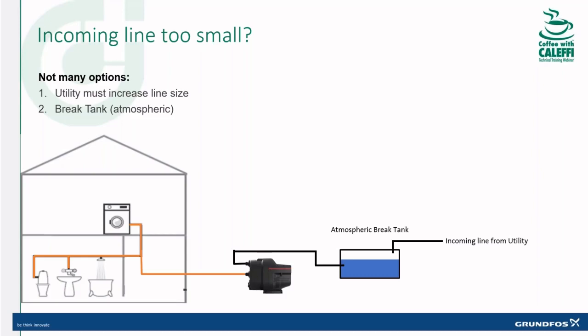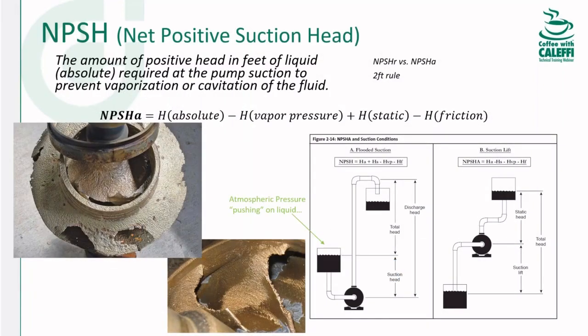And Reece, didn't you say like down in Houston, that's a requirement, the break tanks? Yeah, in the Houston Metro, for the piping that's coming from the city, they're required to use break tanks. So they don't get the advantage of taking pressurized water from the city. It's a code requirement around the city of Houston. So everybody's got to have a break tank. Interesting. Yep. Okay.